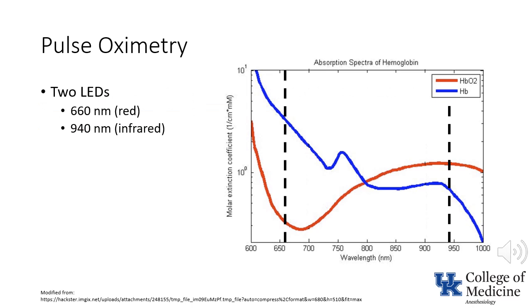Conventional pulse oximetry involves two light-emitting diodes, one of which emits light in the red band and the other of which emits light in the infrared band. Oxyhemoglobin absorbs less red light than reduced hemoglobin — you know this because arterial blood, which has a higher partial pressure of oxygen, is brighter red than venous blood. On the other hand, oxyhemoglobin absorbs more infrared light than reduced hemoglobin.